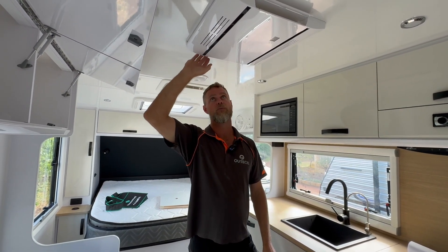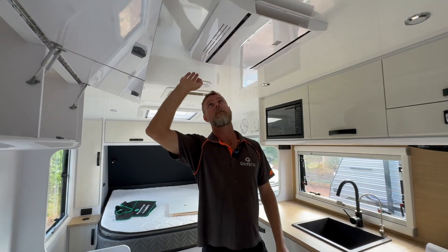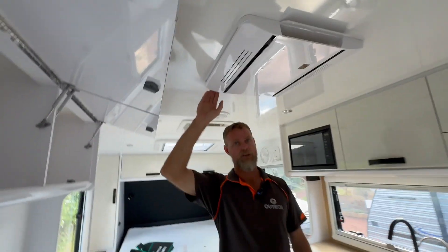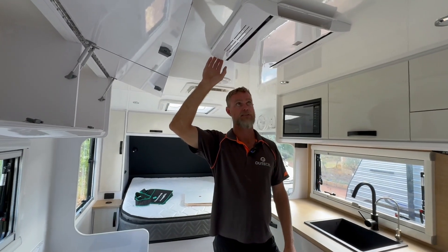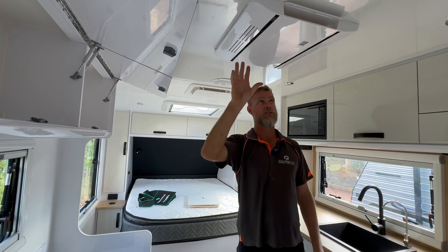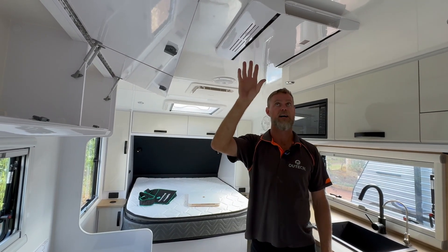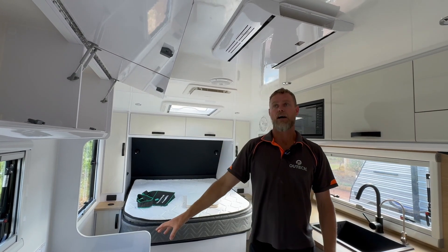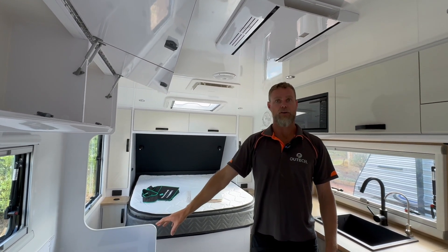This is a Tel-Air air conditioner, which is not a soft-start version. It's not an inverter style — it's basically an on-off unit. So with on-off style air conditioners of this nature, we always install soft starters into them, which looks after the health of the compressor.